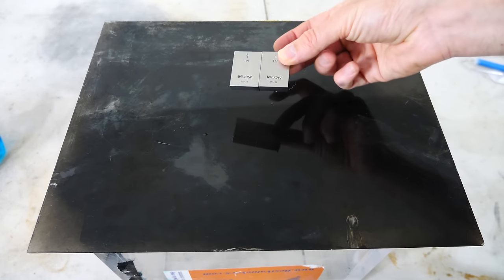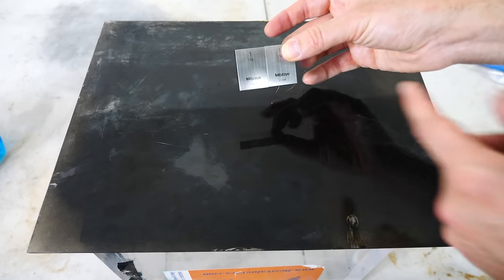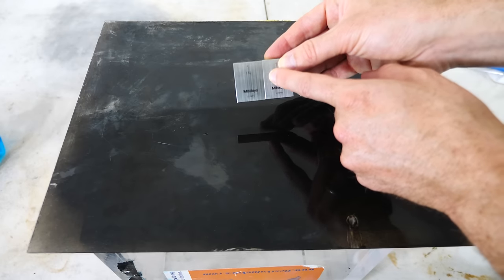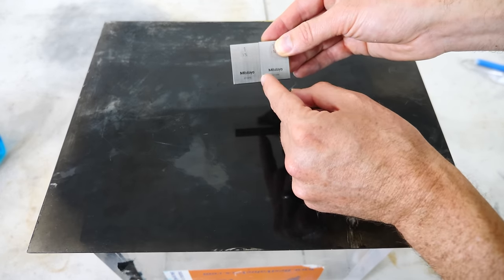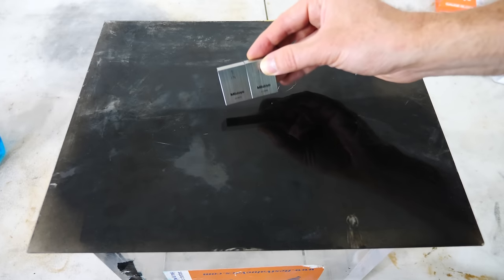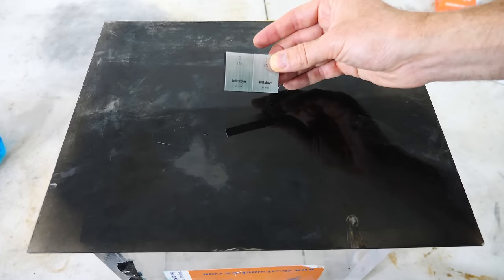For example, if I needed exactly two inches, I can just wring these together. And you can know that as long as they wring together, then that surface is a good surface to use and you don't have to add any additional length by combining them together. So there's no correction factor that you need to do with them.